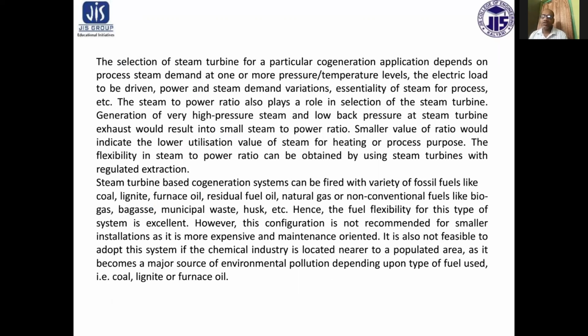The selection of steam turbine for a particular cogeneration application depends on process steam demand at one or more pressure temperature levels, the electric load to be driven, power and steam demand variation, essentiality of steam for process, etc. The steam to power ratio also plays a role in selection of steam turbine.